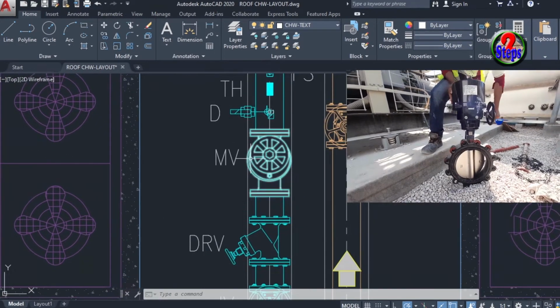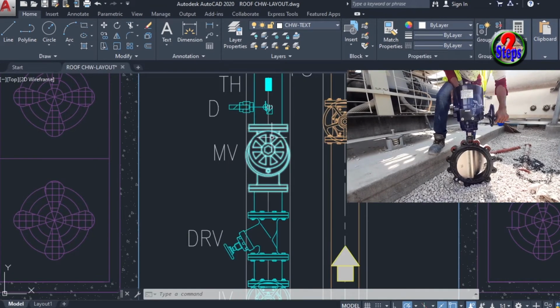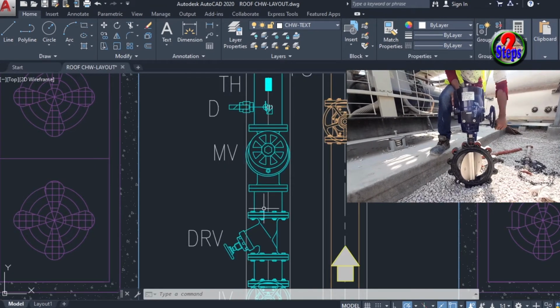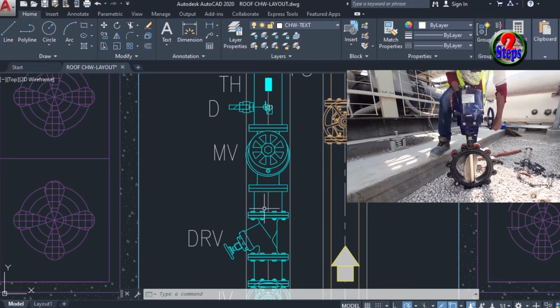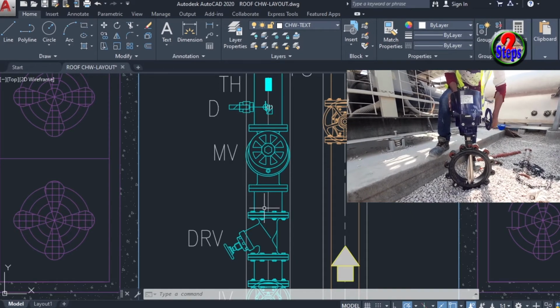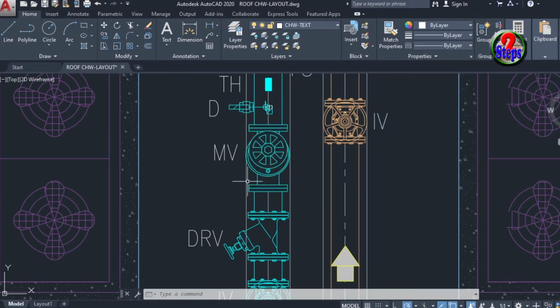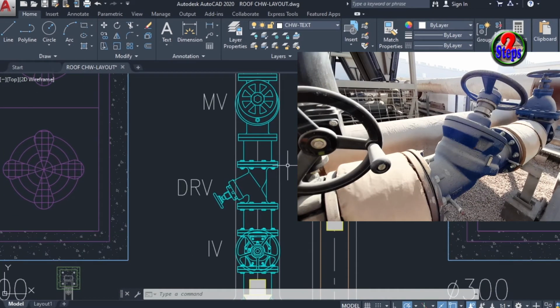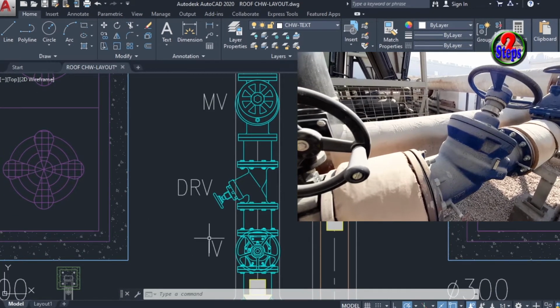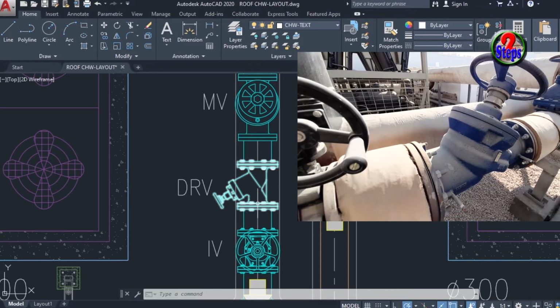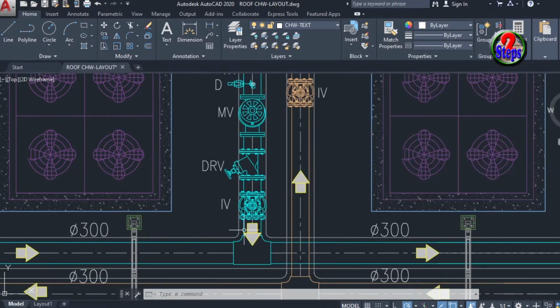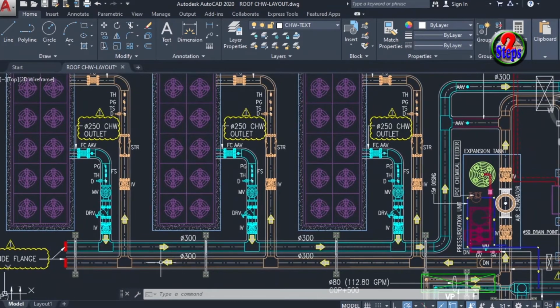And after that, the motorized valve. Drawing symbol is MV. This is a butterfly motorized valve. It can control water flow automatically. After that, the double regulating valve. Drawing symbol is DRV. And at the end, the isolation valve, then connect to the chiller outlet header that goes to the secondary pump section.